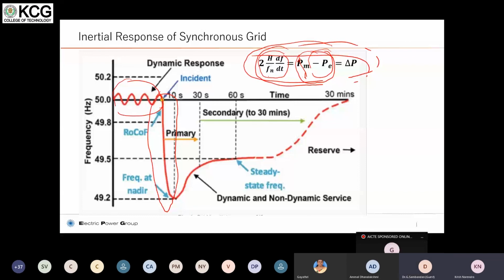Now, in order to support this left hand side of the equation, you can balance it out with right hand side quantities such as the electrical power that is input into the system during the inertial support. These powers can be very nicely contributed by IBR devices, such as even the battery backup. Nowadays it's so intelligent that it can provide extra power when it is needed, and it can modulate the system power so that the inertial balance will be obtained, basically by providing virtual inertia to the system. It's nothing but the power balance, right?